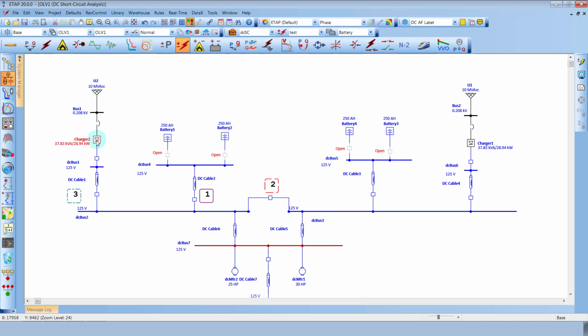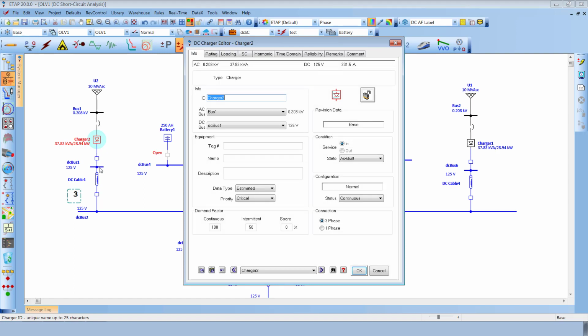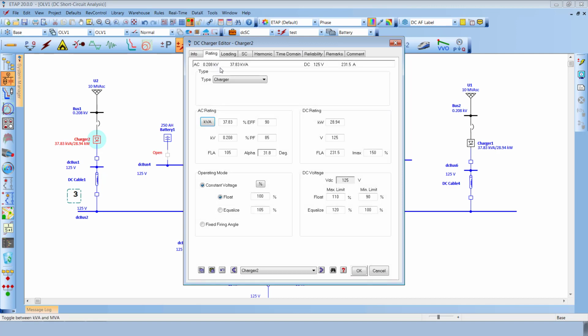The DC chargers are modeled as a voltage-dependent current source that inject current to the system based on its bus terminal voltage. The rating page of the DC charger comprises the voltage and the full load amps and the corresponding maximum and minimum voltage limits specified accordingly.